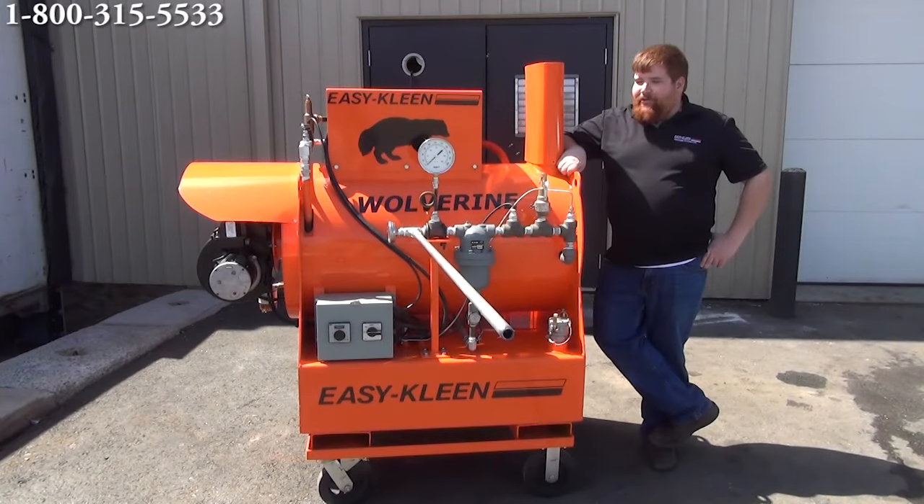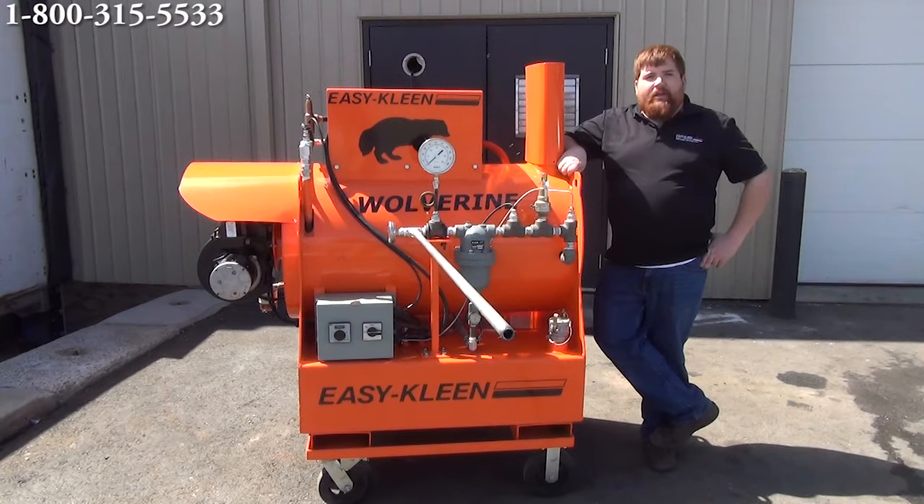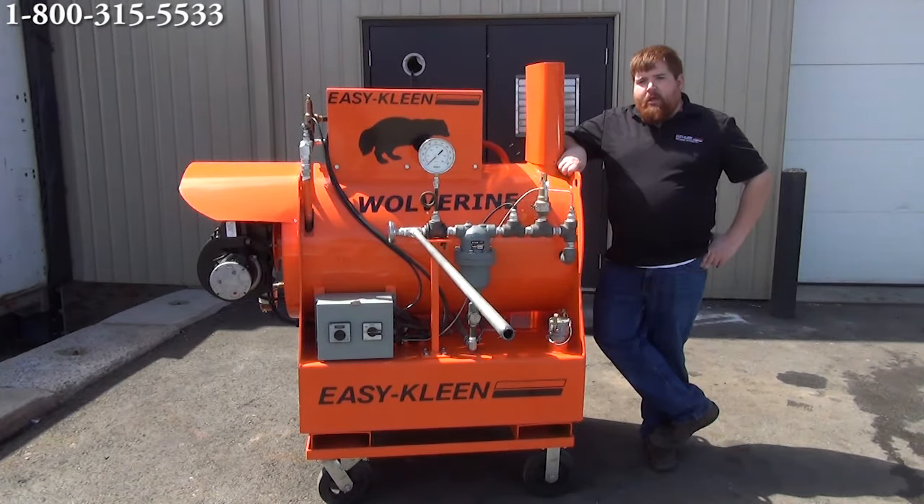Hi, I'm Josh from Easy-Kleen. Today we're here to introduce our new Wolverine steam generators. These generators are available in 10, 20, 30, 40, and 50 boiler horsepower. The one we're going to be demonstrating today is a 30 boiler horsepower. It's an oil-fired unit. This machine, when operating, will have about 350 degrees of dry steam coming at the end of the pipe here. We're going to start it up and do a little video.